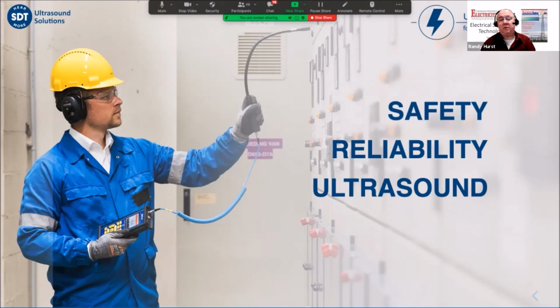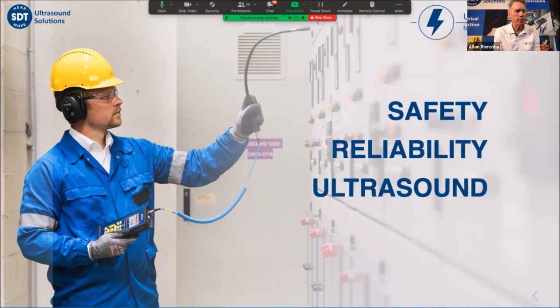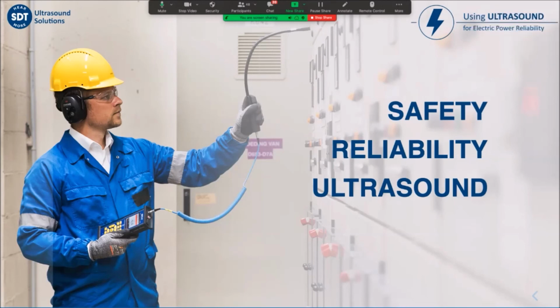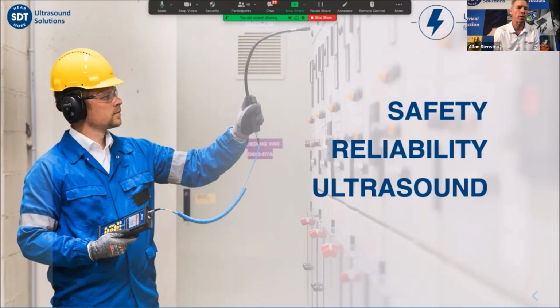Can you mount the unit in the panel, and for how long? At SDT we have a different solution for mounting inside the panel, a product called Vigilant. Vigilant connects up with airborne ultrasound sensors, and these sensors heterodyne the signal right on the sensor, providing either a 4 to 20 milliamp or a 1 to 10 volt output. That sensor can be mounted permanently inside an MCC panel and monitored using a PLC or any other common measurement device, or you can plug them into our Vigilant, which gives you a dashboard showing all of the potential for partial discharge activity.